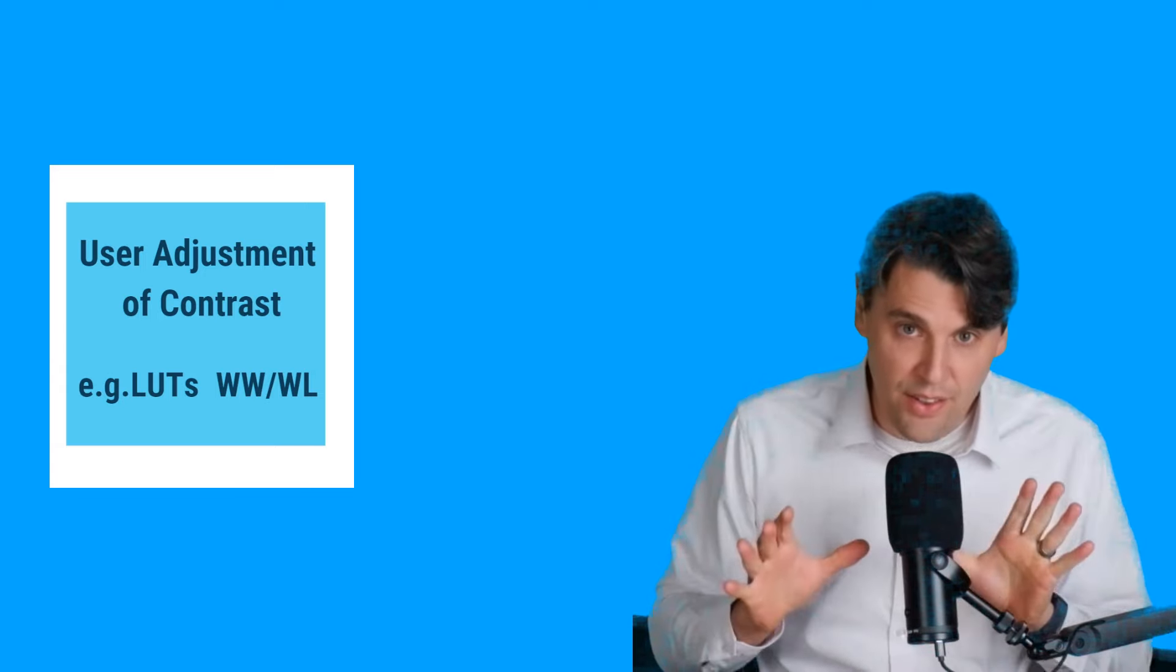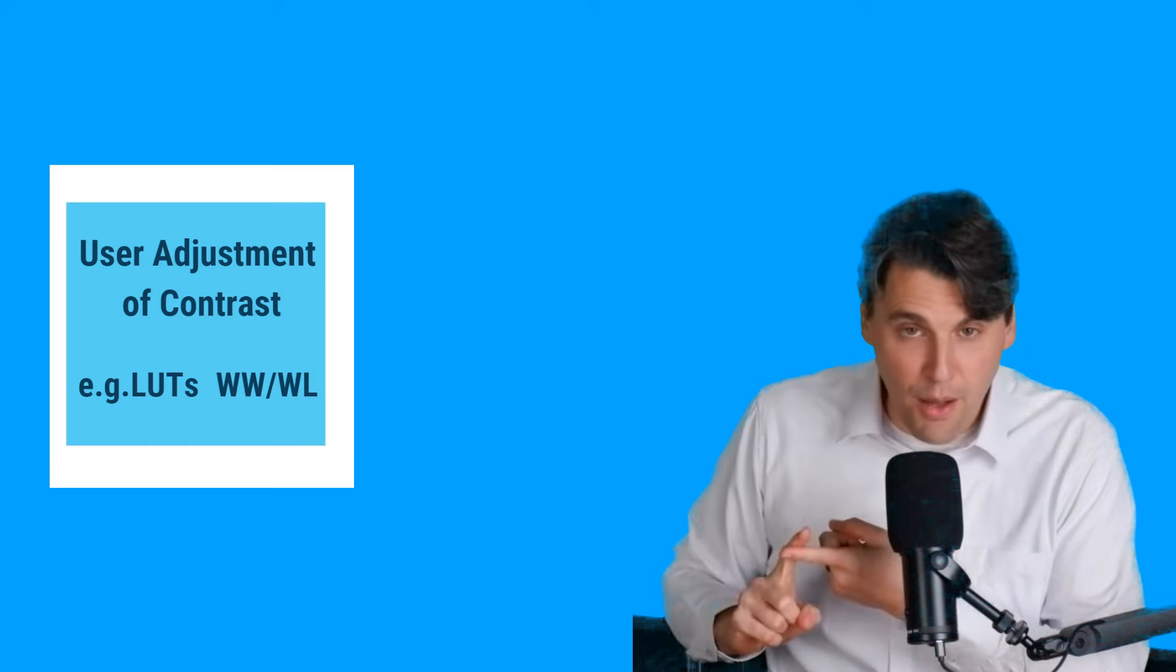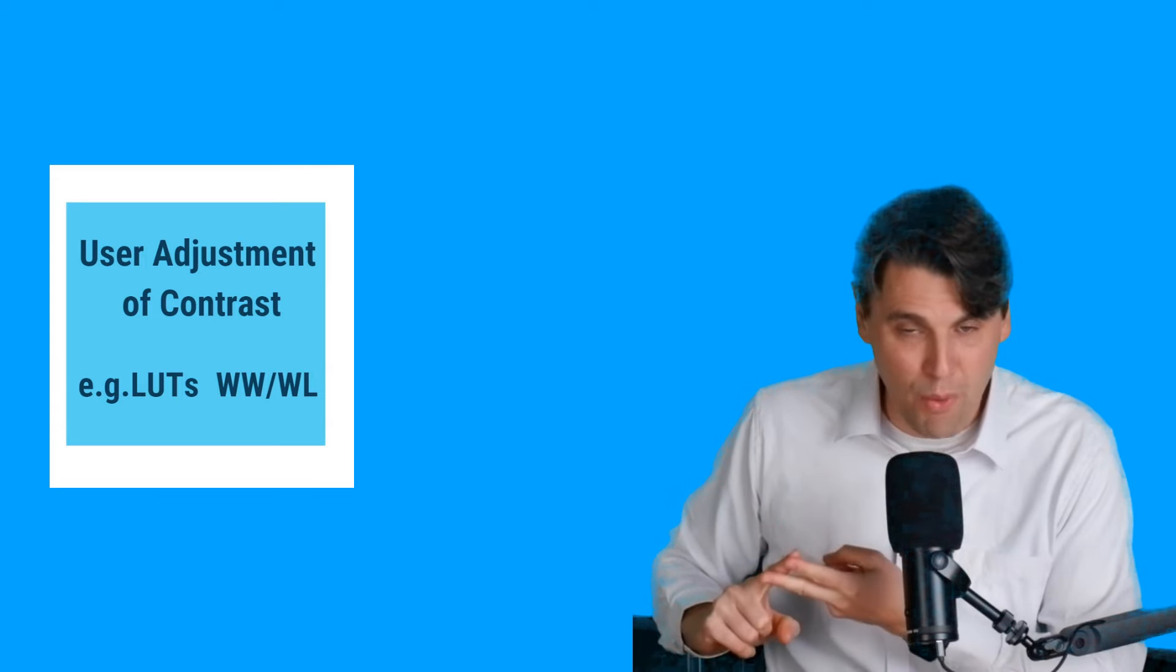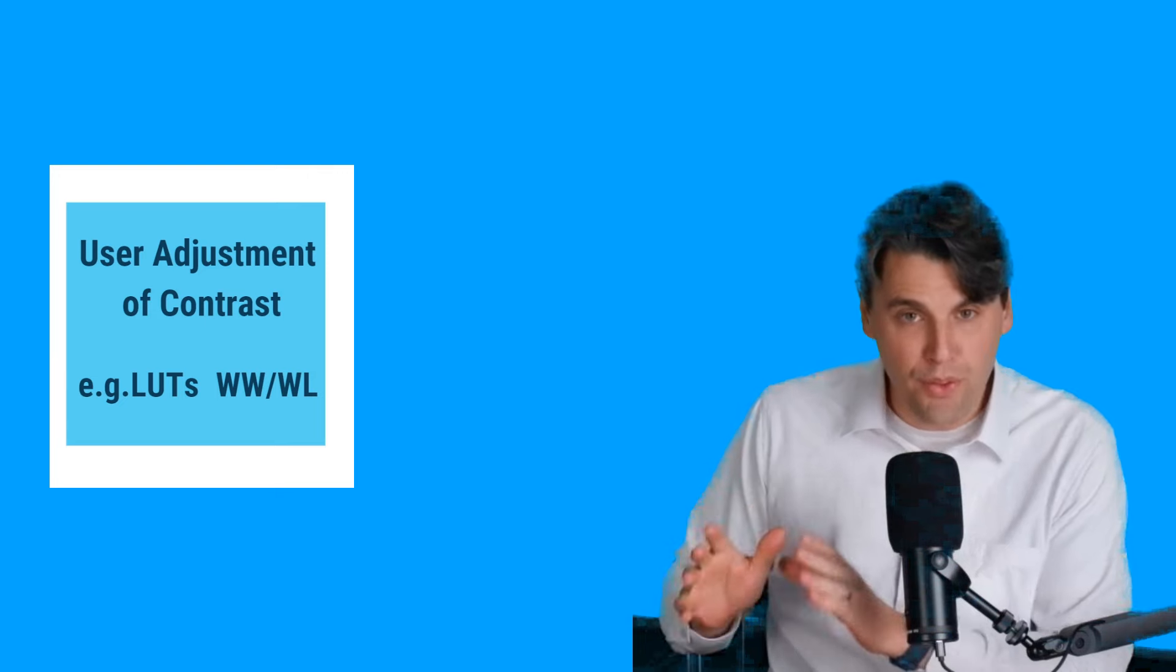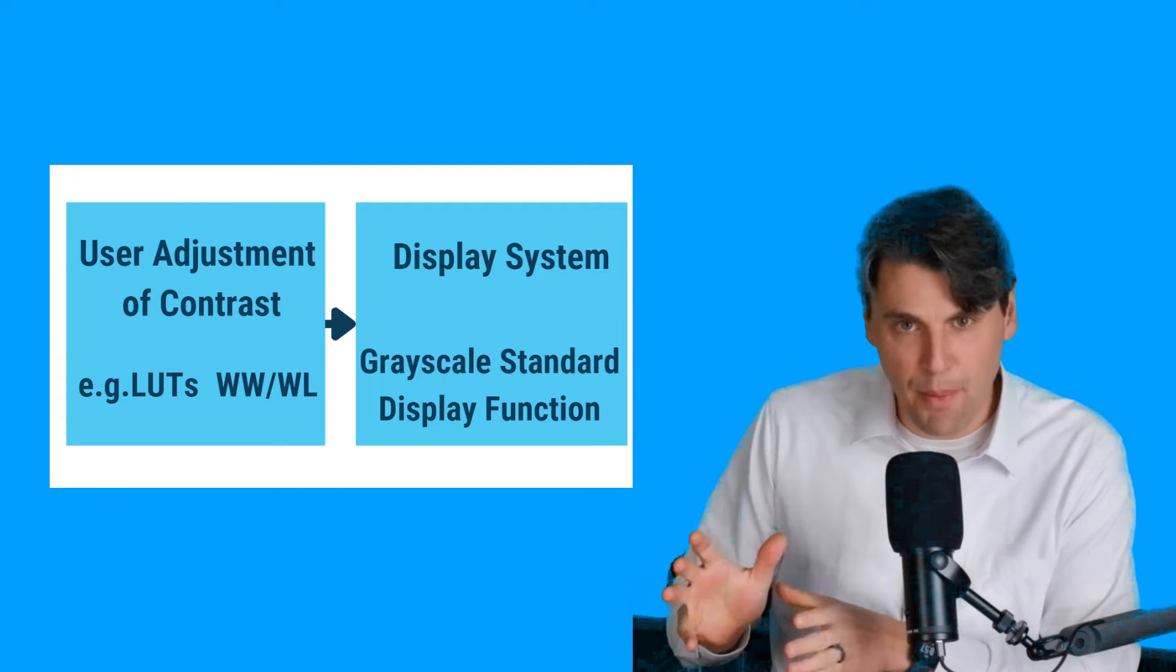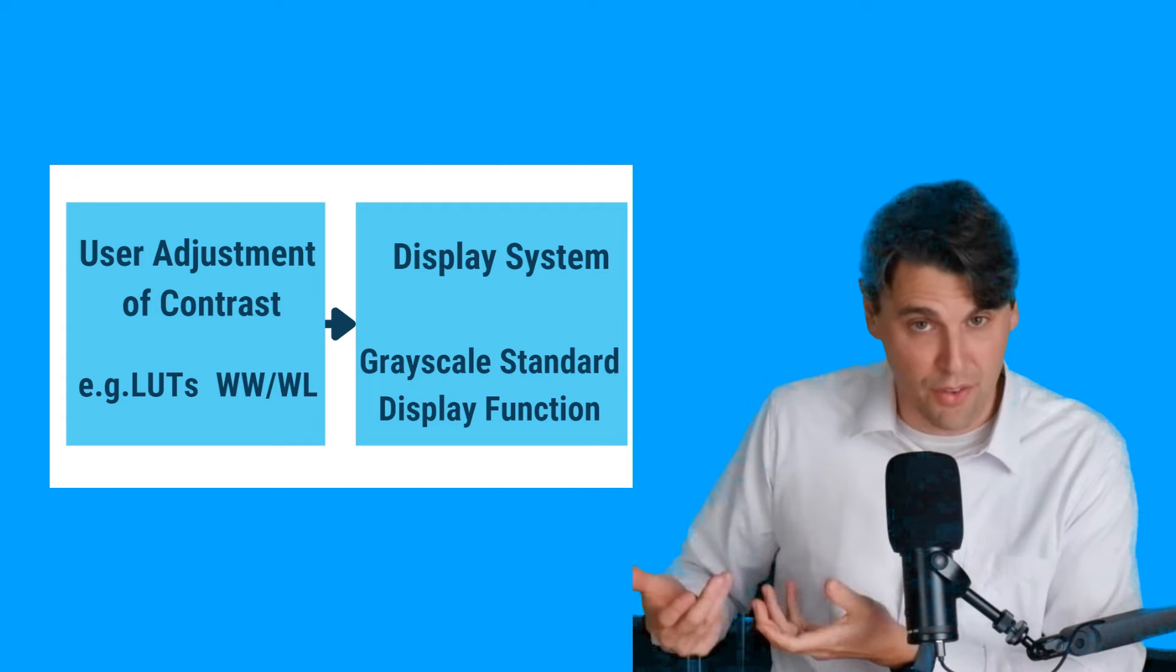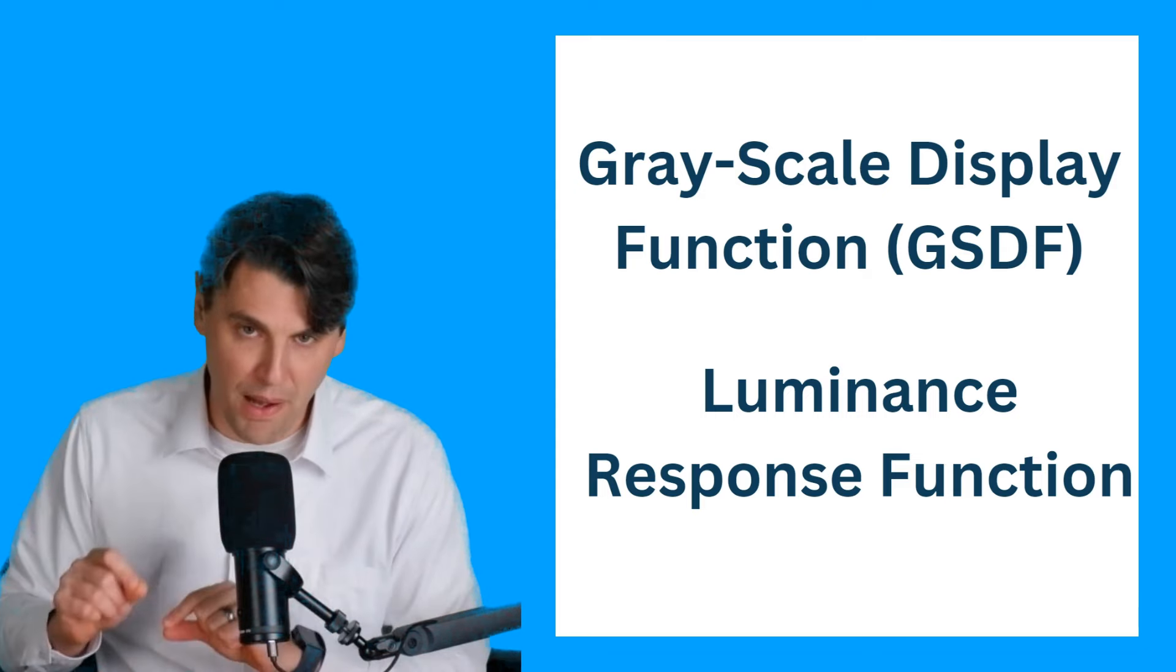The user can adjust the contrast in the image. They can do that with lookup tables. See our video on LUTs. They also can do that with window width and window leveling, changing the window width and window levels. Both of those things can be done on the display side. There's then a separate lookup, which actually maps to what's called the grayscale standard display function. We can also more generally call the luminance response function.